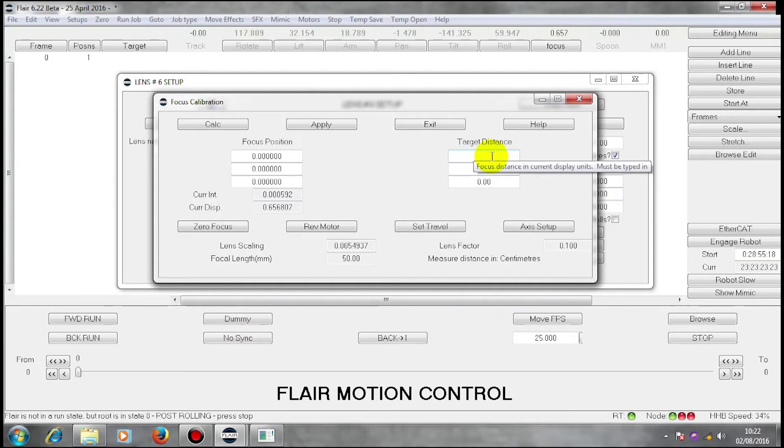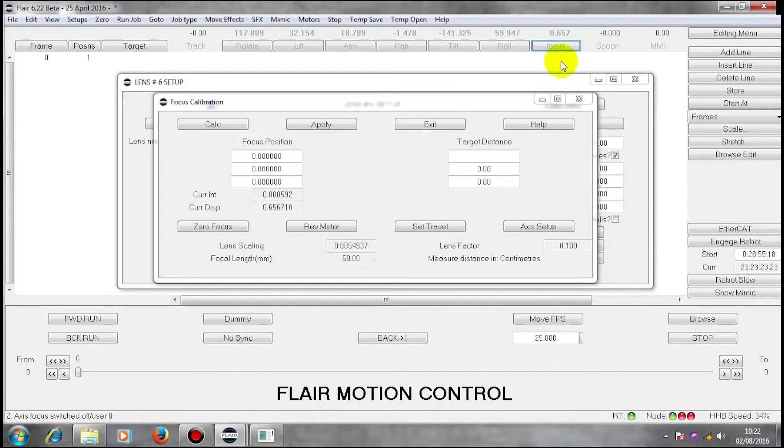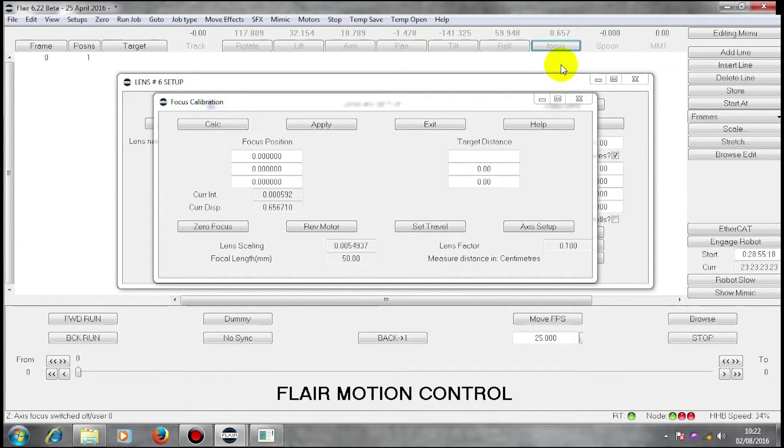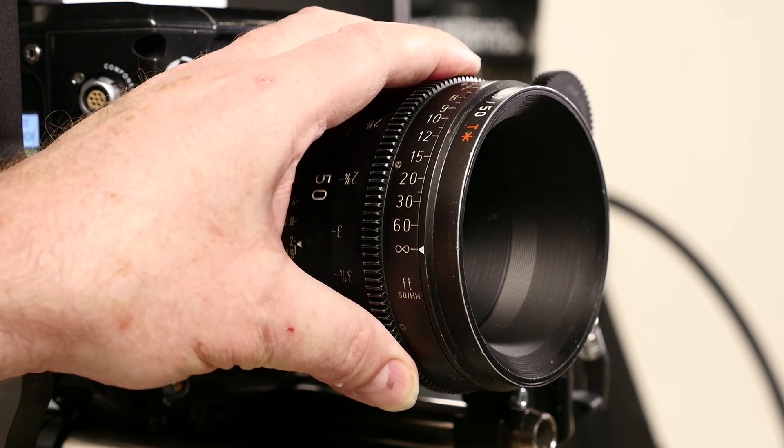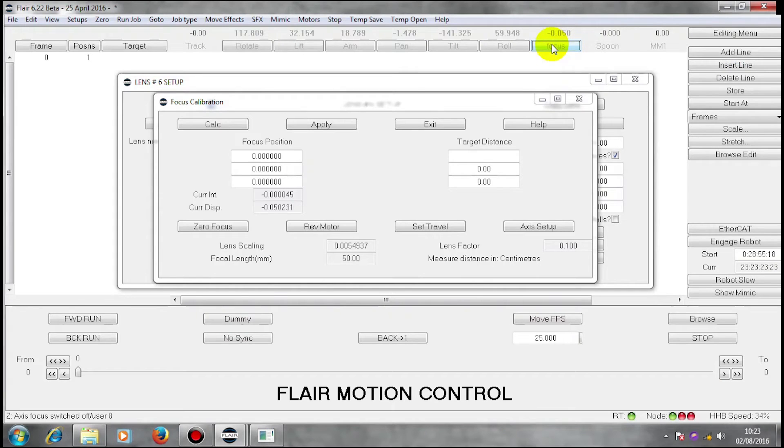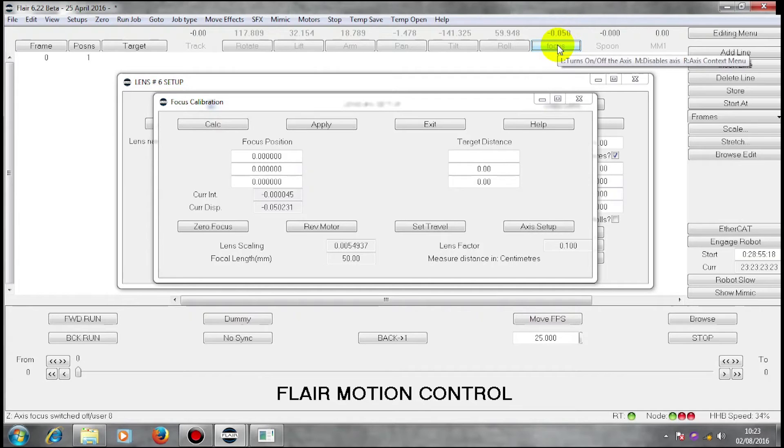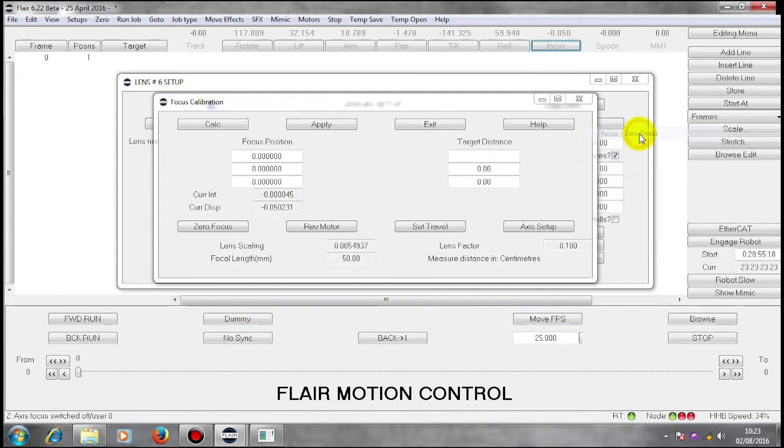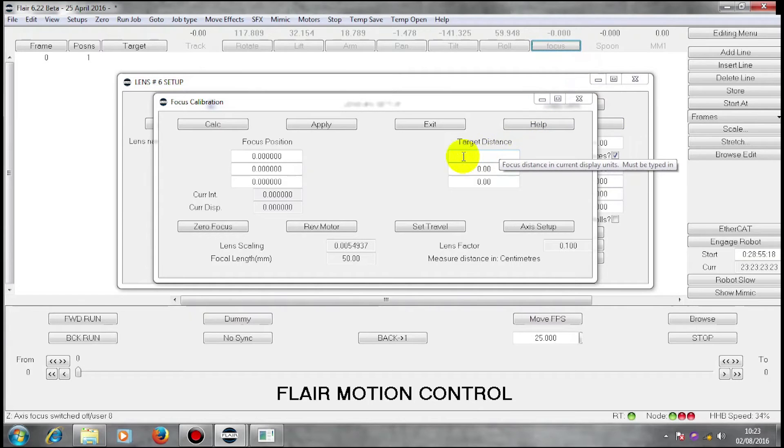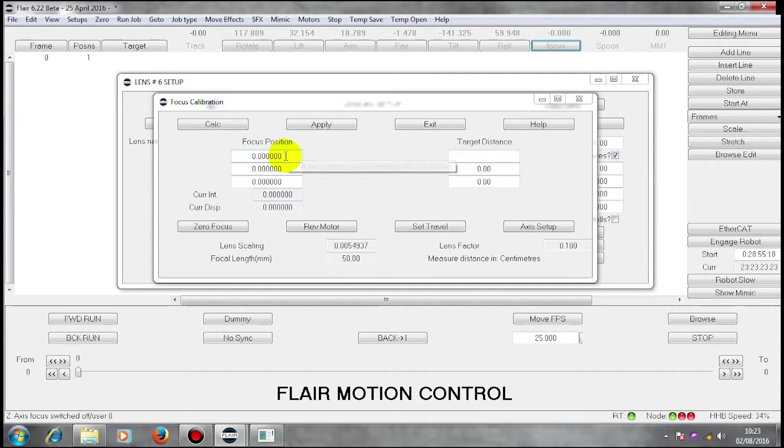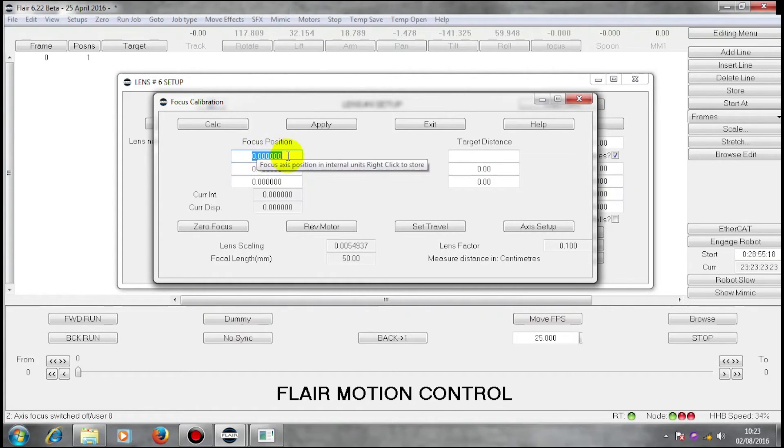In order to get the first target distance, I have to be at infinity. And in fact, what I'm going to do is I'm going to turn off my focus axis so I can back drive the motor. And I'm now going to put the lens on infinity by physically moving the lens. I've now put the lens on infinity but the focus axis doesn't read zero. So what I'm going to do now is I'm going to directly zero the lens at infinity. This gives me the end of my travel and the zero reference or home position for my focus axis. Because that is effectively infinity, there's no numbers there. My focus position for this, read from the motor, is left click, right click, store, zero.